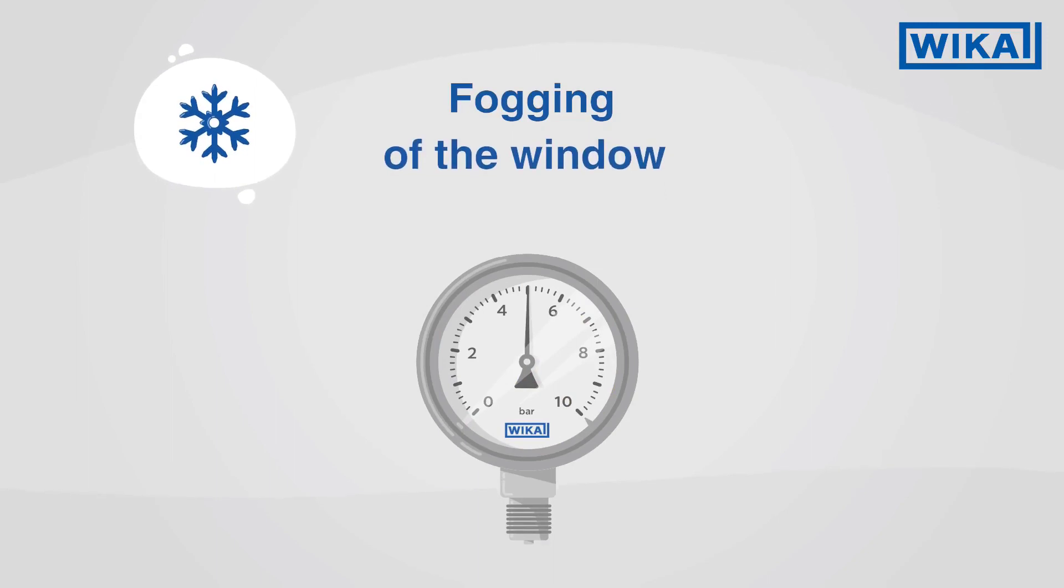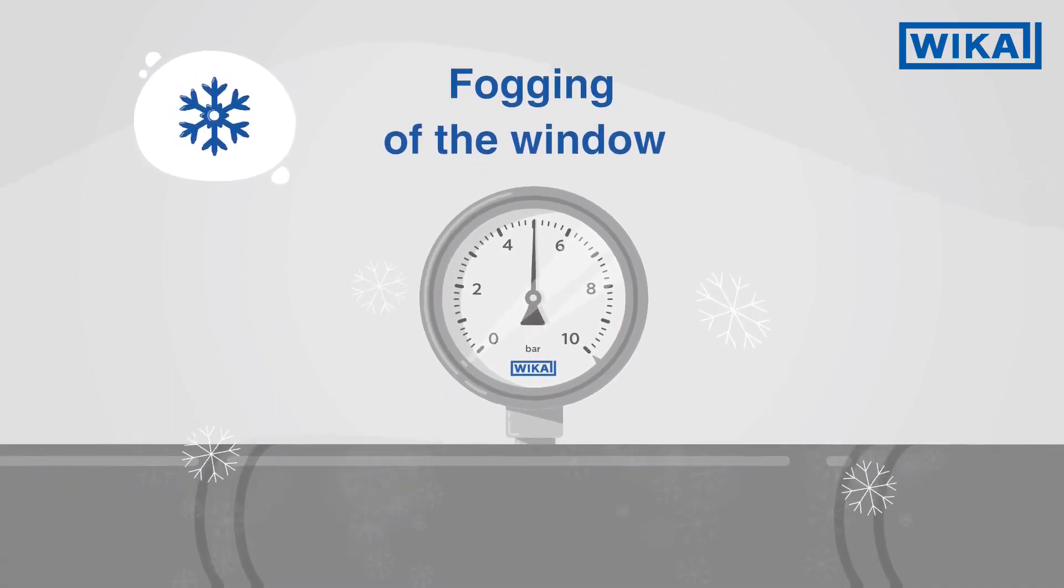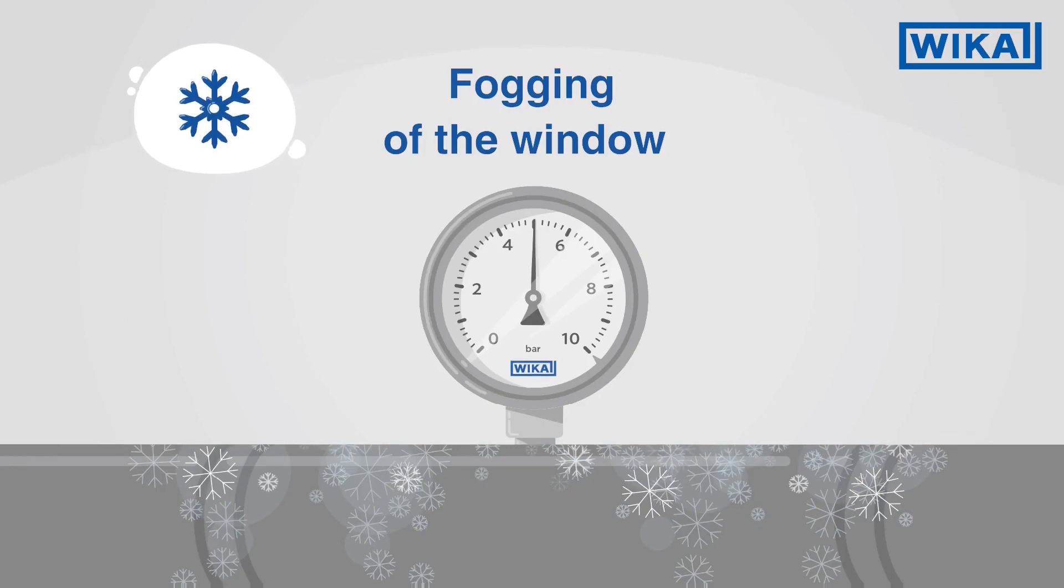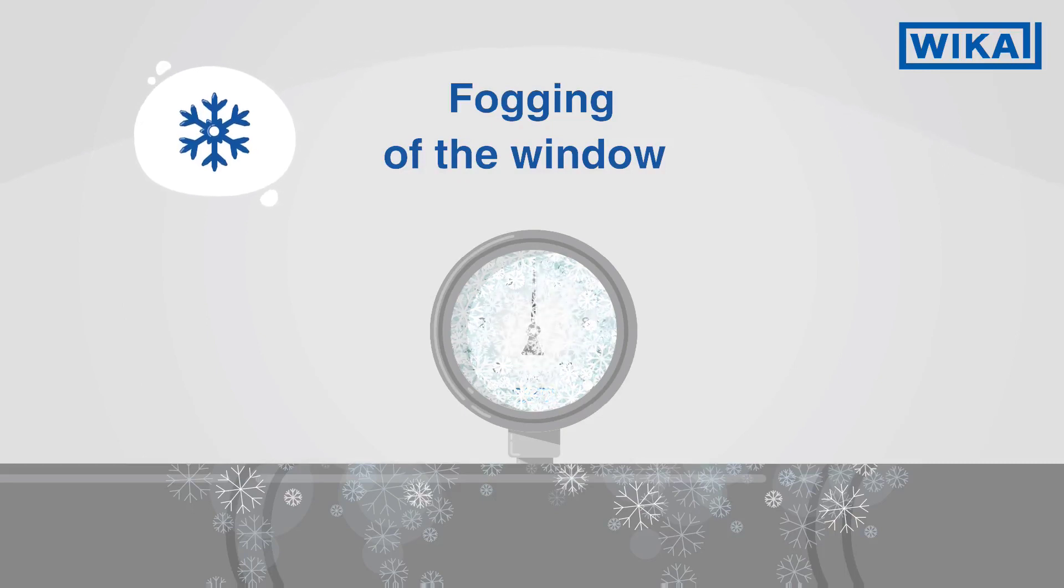Fogging of the window. Filling is also recommended when the pressure gauge is being used with very low ambient temperatures. In this case, condensation can build up on the inside of the window, which can reduce readability or even cause the entire window to frost over. The filling liquid ensures that frosting of the window is prevented and unimpeded readability is guaranteed.